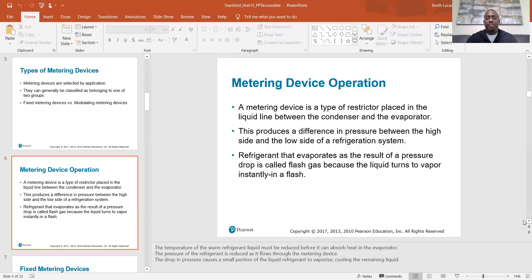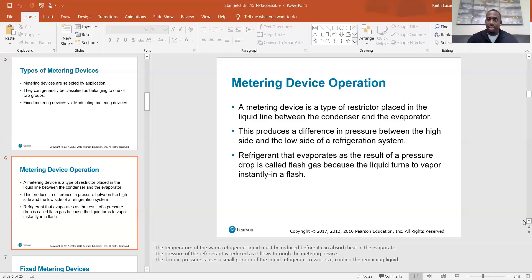Fixed metering devices are considered critical charge systems, meaning the amount of refrigerant in the system is critical. If you're a little over or a little under, that's going to be much more problematic on a fixed metering device than on a modulating metering device, which can adjust for those changes. On a TXV or modulating metering device system, it can dial back the amount of liquid it allows in.